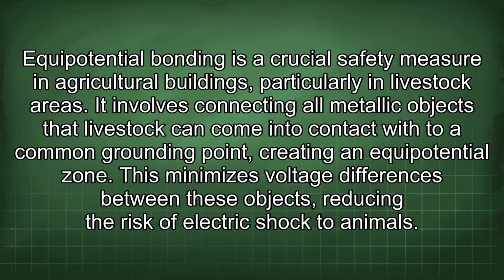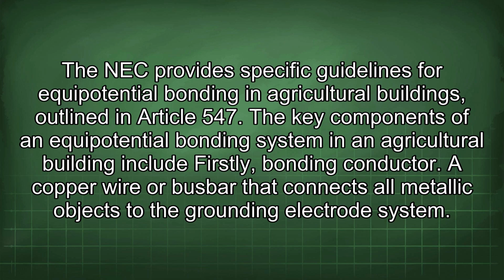It involves connecting all metallic objects that livestock can come into contact with to a common grounding point, creating an equipotential zone. This minimizes voltage differences between these objects, reducing the risk of electric shock to animals. The NEC provides specific guidelines for equipotential bonding in agricultural buildings outlined in Article 547.